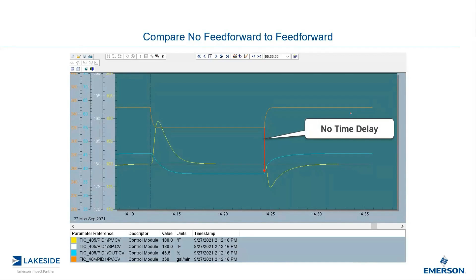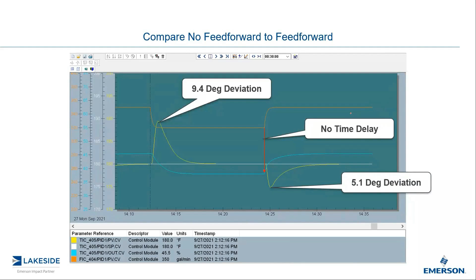Whereas with feed-forward, there is no time delay. As soon as the load flow changes, I move the output right away because I know that disturbance is coming. And once again, we went from a 9.4 degree deviation to 5.1, give or take - a significant improvement in load disturbance rejection.